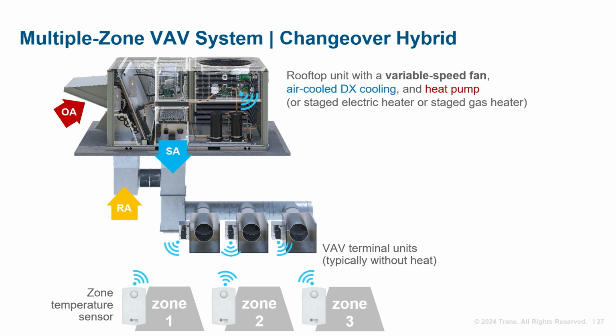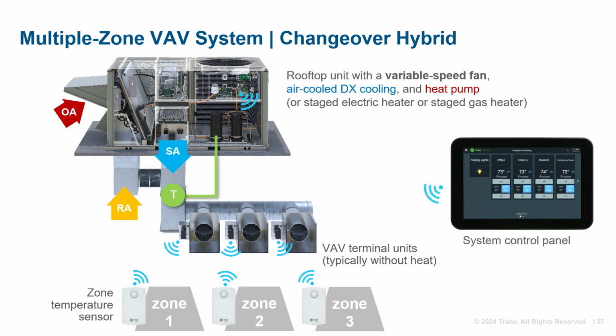The unit draws recirculated air from the return air plenum and mixes it with outdoor air. This mixture is then conditioned and circulated through the supply ductwork and VAV boxes into the occupied zones. For this changeover hybrid system, a control system uses a voting strategy to determine whether the rooftop unit should supply cool air down the duct or change over to supply warm air down the duct.